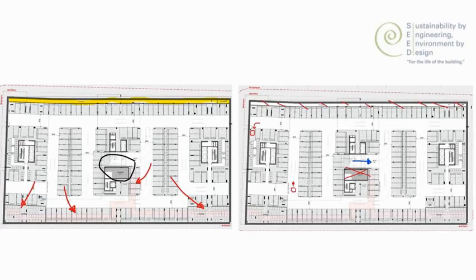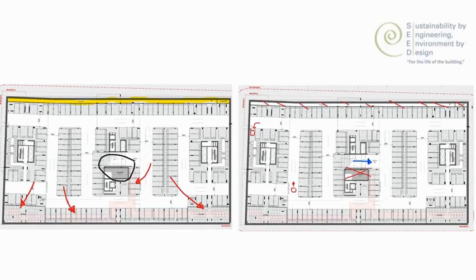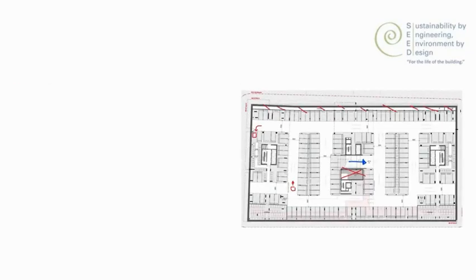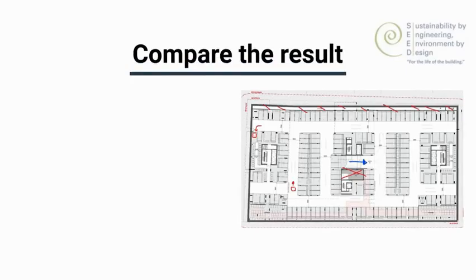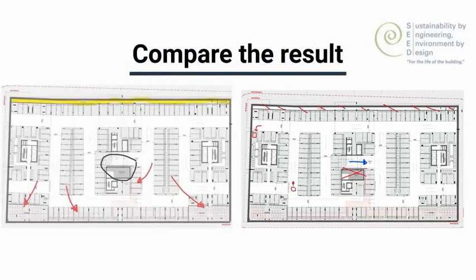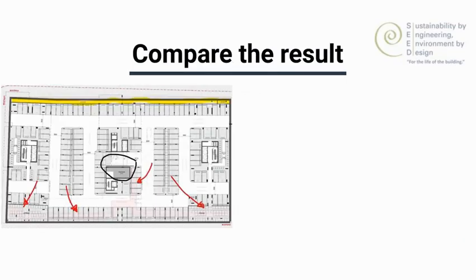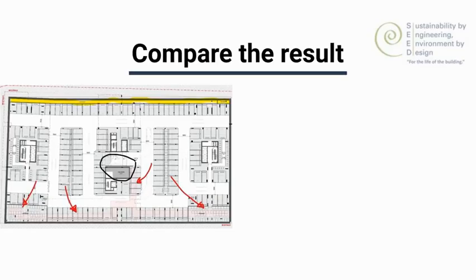Delete the extra excavation, use that ramp in the middle as a fresh air supply. Down the bottom there's a red square — we may need a jet fan to help the circulation. And of course, extraction in that top left-hand corner. Once you've got these two systems, you can compare the results: what have we saved, what's it going to cost to build, what's the impact on the program? This is where we get the opportunity to determine that we have value.